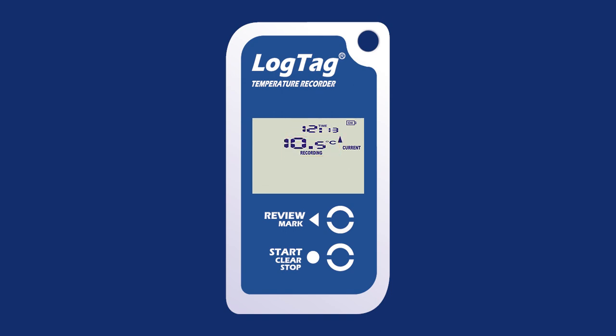If the most recently recorded temperature is above or below the alarm thresholds, a single arrow will appear on the logger indicating whether an upper or lower alarm threshold has been triggered. If an alarm event occurs, the alarm symbol will display along with the Today Alarm Marker.